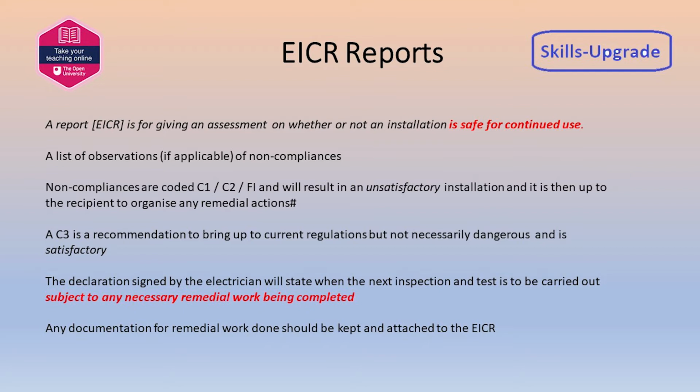FI, further investigation required without delay, and in the notes for the person producing the report it says that this should be recorded in section E as, again, unsatisfactory. And there is one satisfactory outcome, C3, although improvement is recommended.